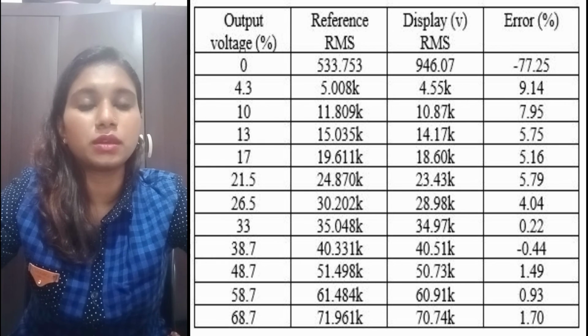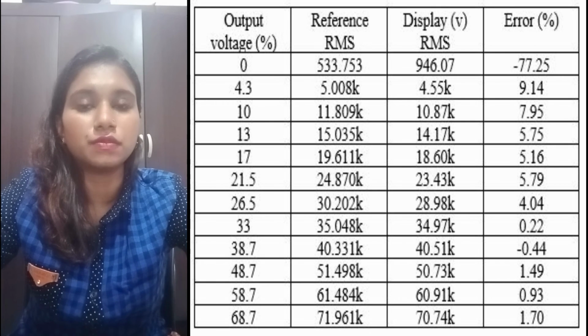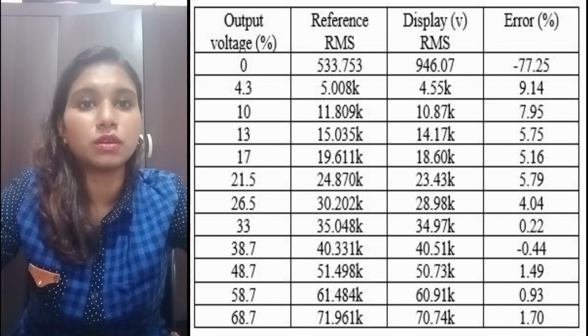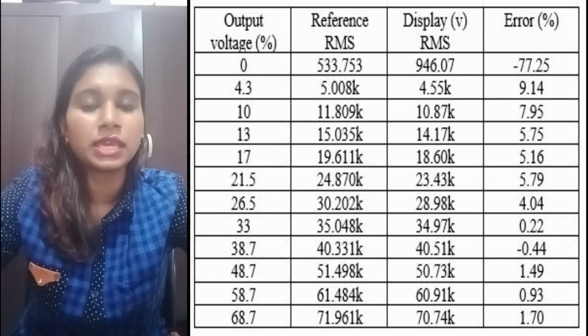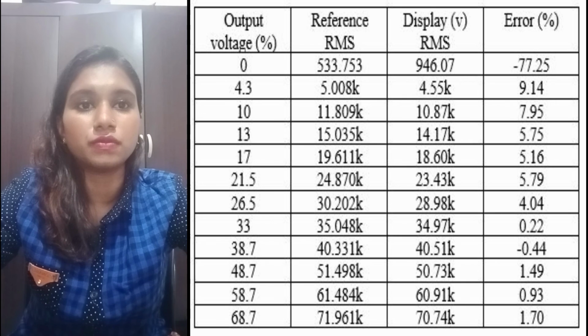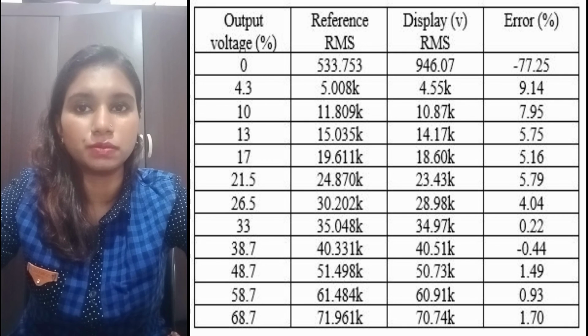The value of peak over square root of 2 is not used for calculation since the value of reference and the value of display are totally different and the error is also very large. This might be caused by the source voltage not being constant, so the waveform produced does not achieve the same value as the reference value. On the other hand, the major factor might be some heat in the system, which tends to interrupt the readings obtained.